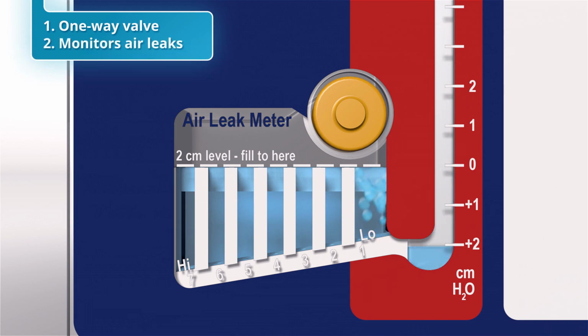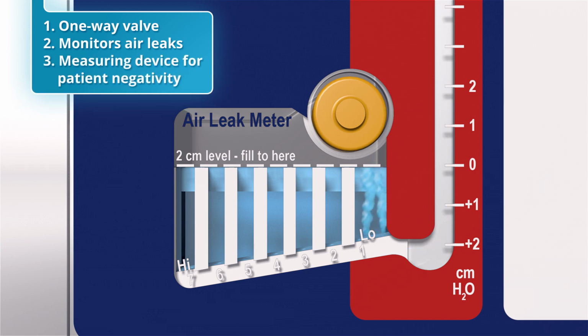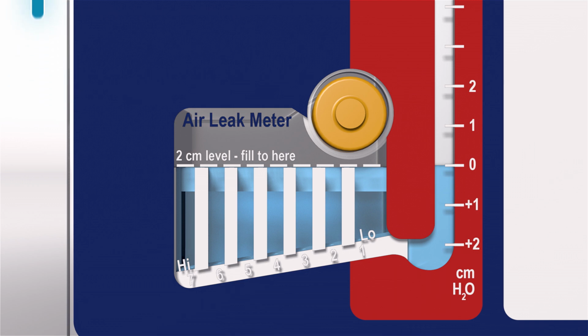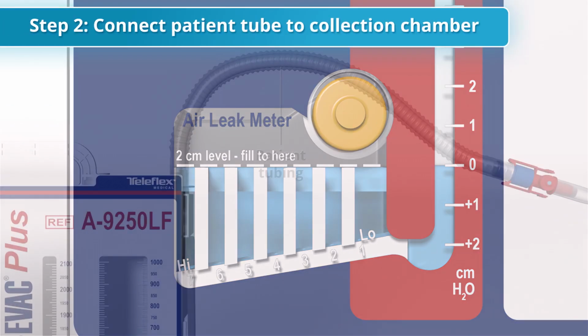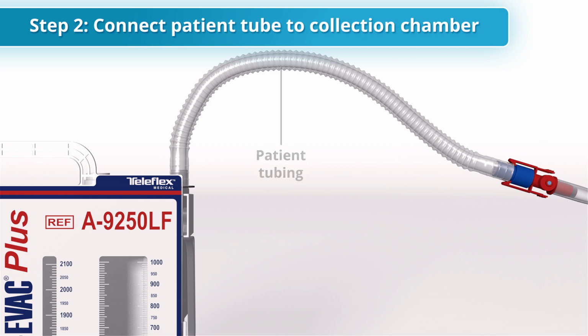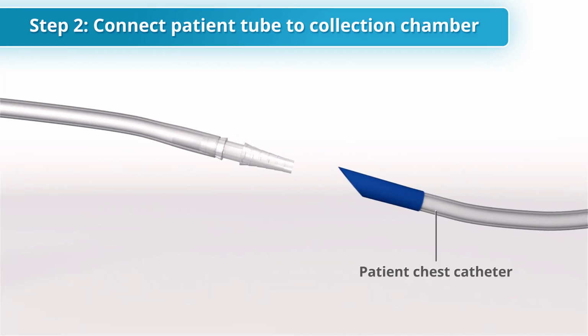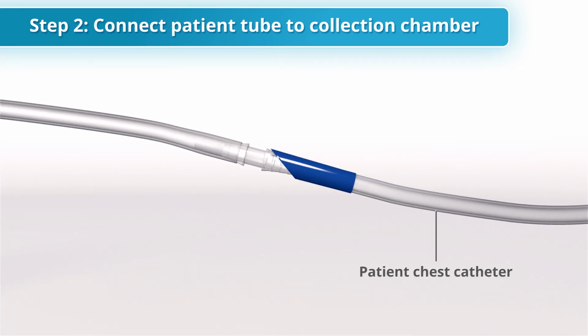Second, utilizing the patented 7-column air leak meter, it monitors the degree of the patient's air leak. Finally, the small arm of the water seal chamber serves as a measuring device for monitoring patient negativity, which is the negative pressure in the patient's pleural space. Now that the water seal has been established, it is safe to connect the patient to the device. The second step in device setup is to connect the 6-foot patient tubing to the patient's chest catheter. Once connected, the patient is now protected from atmospheric air re-entry.